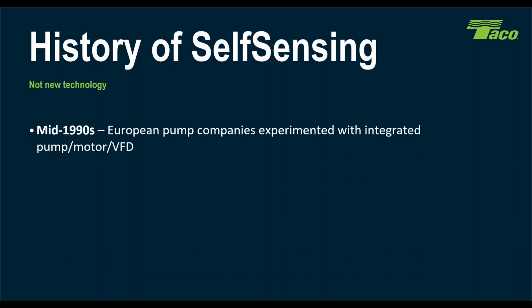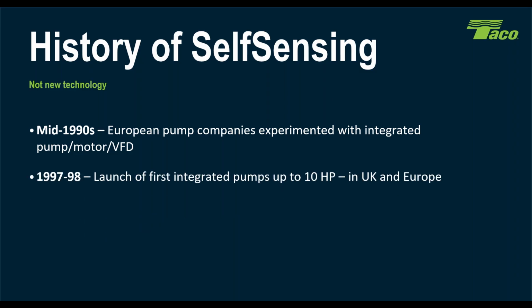Self-sensing was developed in the mid-1990s by a company in the UK by the name of Holden and Brook. Holden and Brook developed it using an integrated pump motor VFD combination, and they used it for quite a while up and through the mid-90s. And it was first launched in the UK and Europe up to 10 horsepower. Over there, they have much smaller pumps because they typically don't do cooling loads the way we do. A lot of their places are heating only, so their pumps are naturally a little bit smaller.